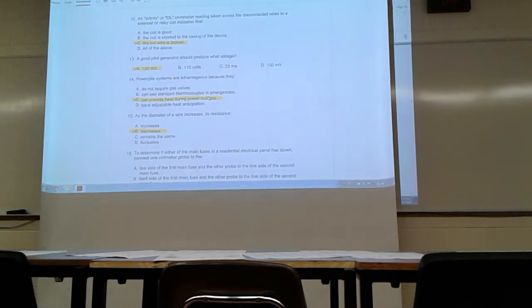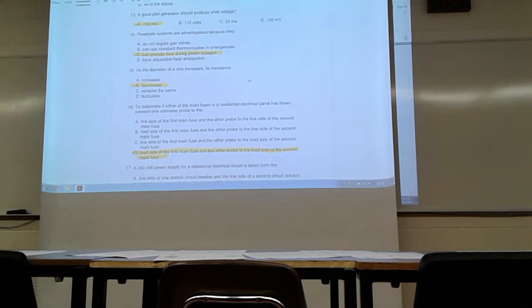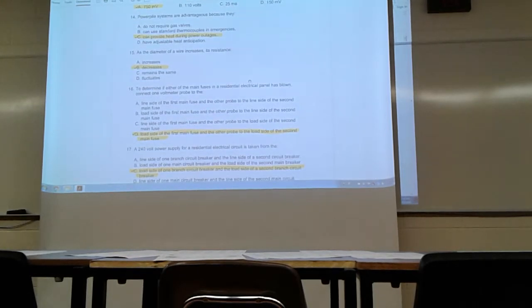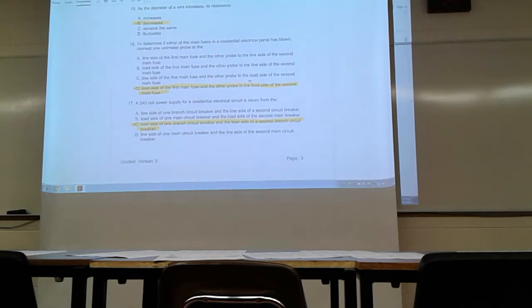13A, a good pilot generator should produce what voltage? 750 millivolts, DC. 14, powerpile systems are advantageous because they can provide heat during power outages because they do not need any external power. They produce their own. As the diameter of a wire increases, its resistance decreases. 16, to determine if either of the main fuses in a residential electrical panel has blown, connect one voltmeter probe to D, load side of the first main fuse, and the other probe to the load side of the second main fuse. 17, a 240 volt power supply for a residential electrical circuit is taken from the load side of one branch circuit breaker and the load side of the second branch circuit.